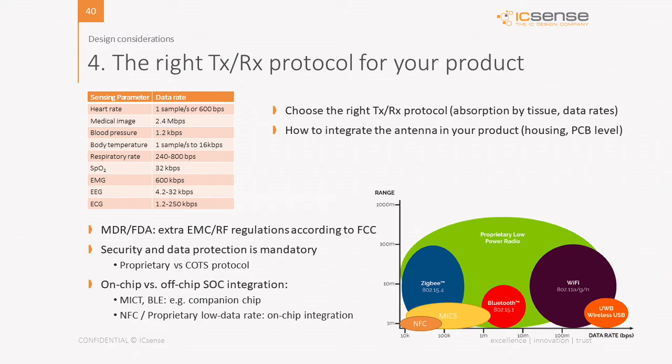Also consider the selection of the right communication protocol. Choose the right communication protocol depending on the absorption of the tissue and the data rates, as mentioned in the table. The most important ones that we see popping up at our customers are either the MICS or the MedRadio.